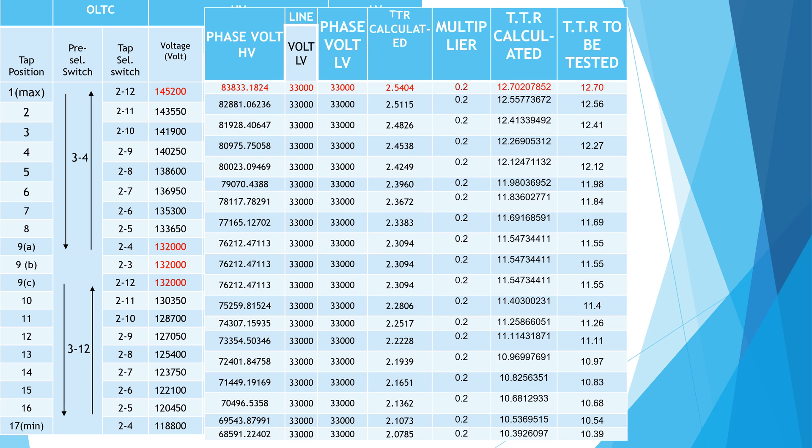This is the rating of a 132 by 33 kV 50 MVA transformer. Here line voltage at tap 1 is 145,200 volts and it is applied on star side. So calculated phase voltage is equal to 145,200 by root 3 is equal to 83,833.18 volts.